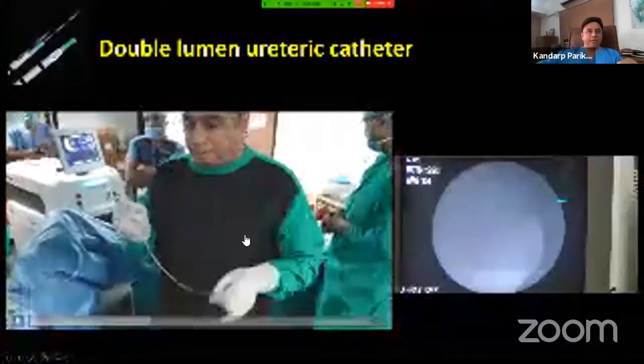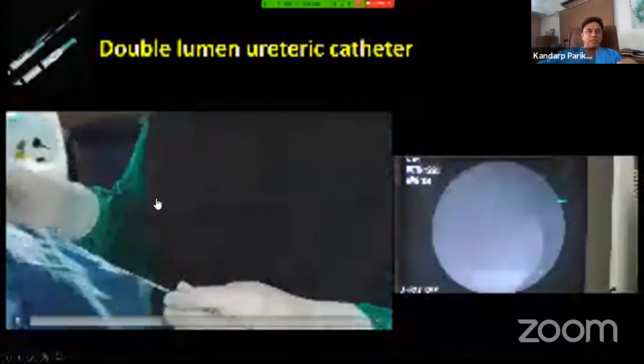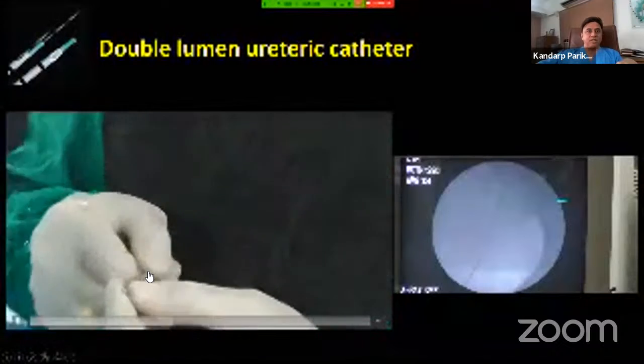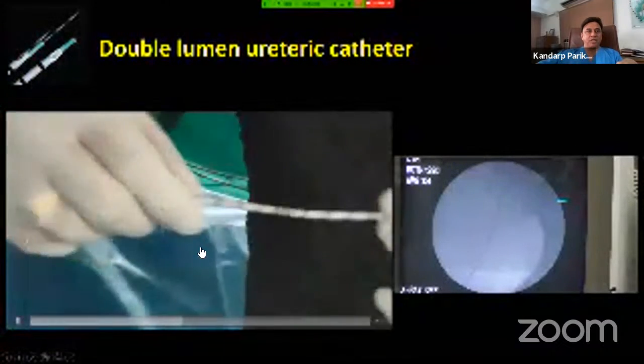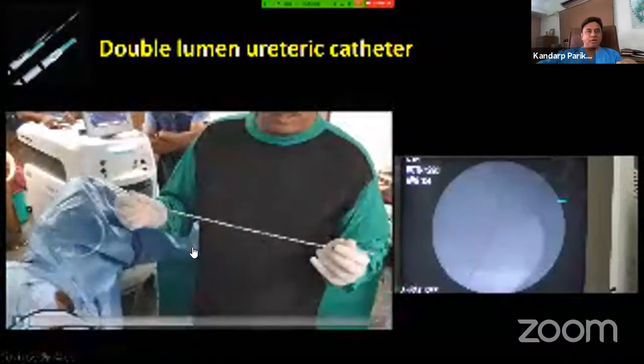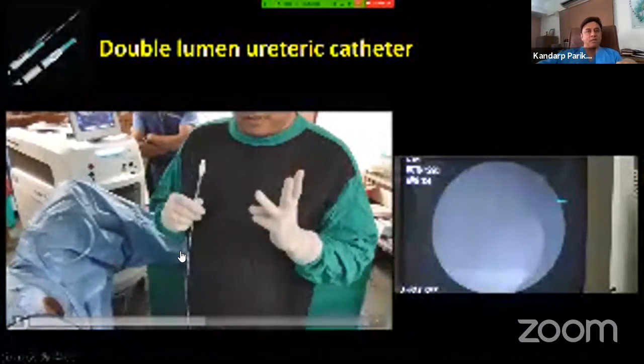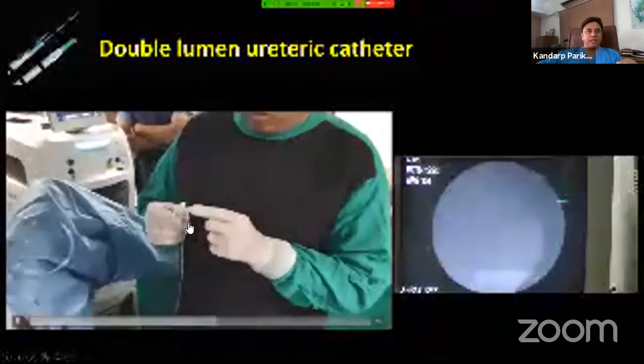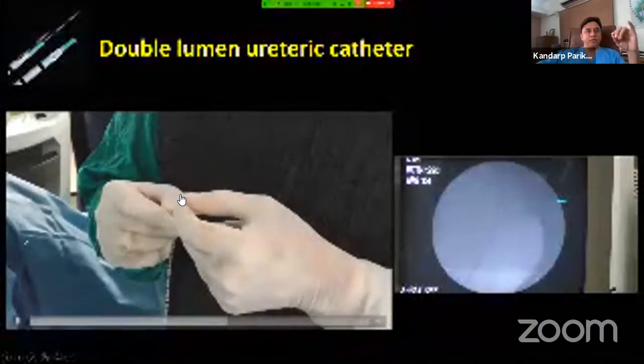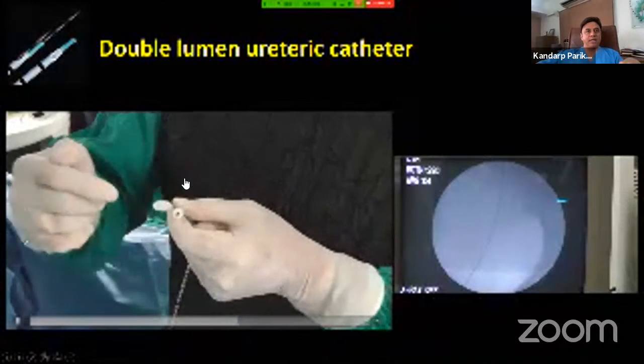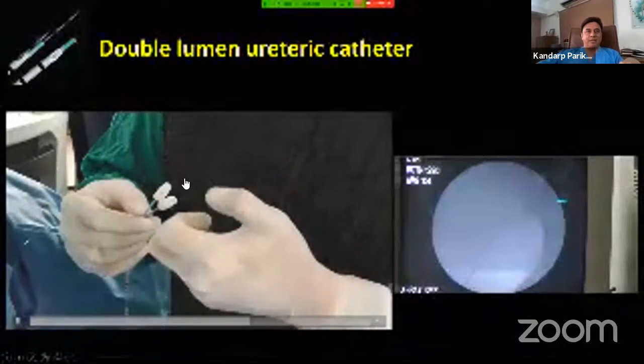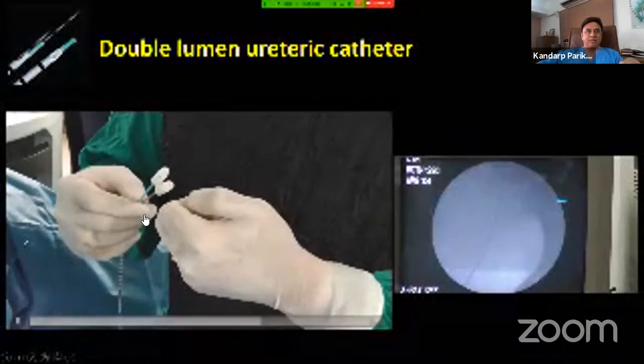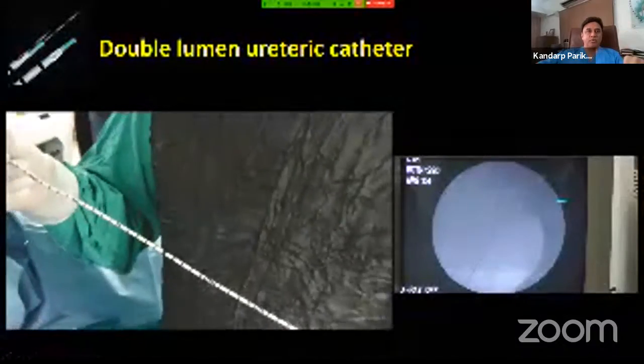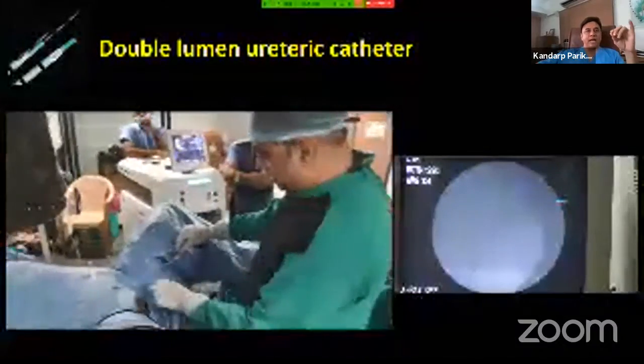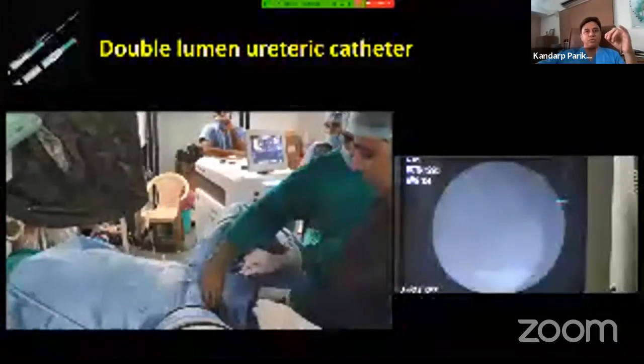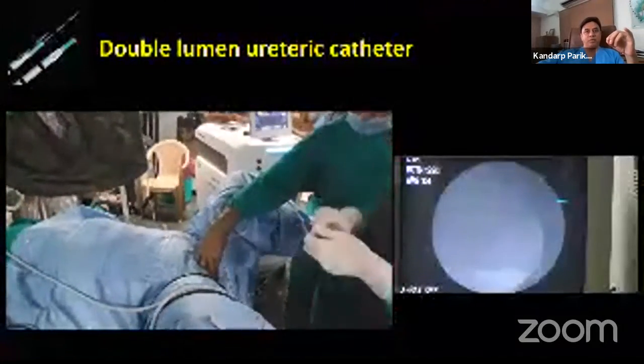This is a double lumen ureteric catheter. It has 2 lumens, that's why it is known as double lumen. The tip is 6 French in diameter. The shaft is 10 French in diameter, and the length is 45 centimeters. It serves 3 purposes. One, you can insert an additional guide wire through this, so if you believe in putting a safety guide wire, it can help you. Secondly, you can inject dye through this, so you can do a dye study, because some institutes do a dye study before they do RIRS. And thirdly, it will dilate the ureter. So these are the 3 purposes you achieve by putting a double lumen ureteric catheter.